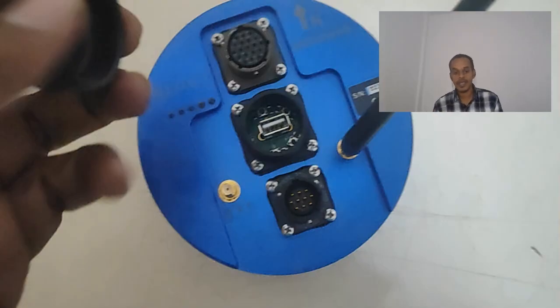These equipments also contain an accelerometer, so they will take the seismic data and also the acceleration data. So these are used for both structural analysis and earthquake monitoring, and also further studies. Now I'll give you a theoretical explanation about the digitizer first.